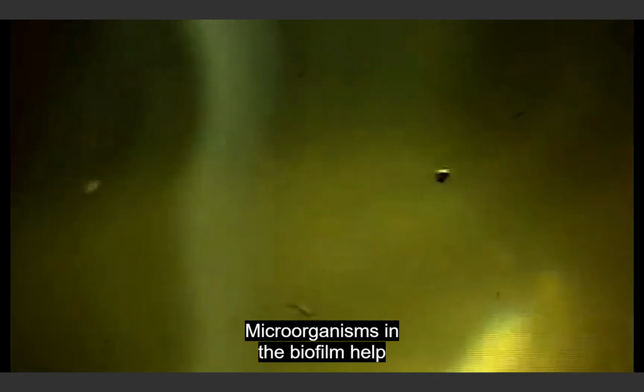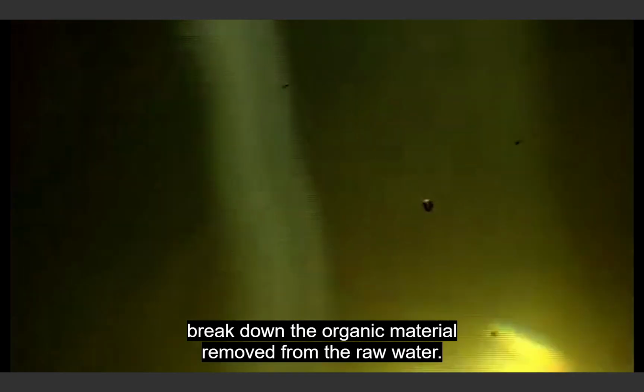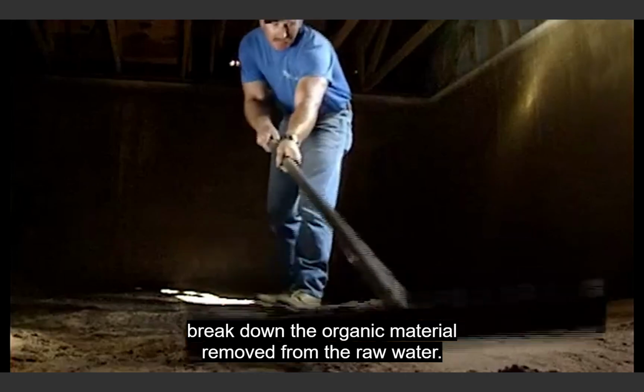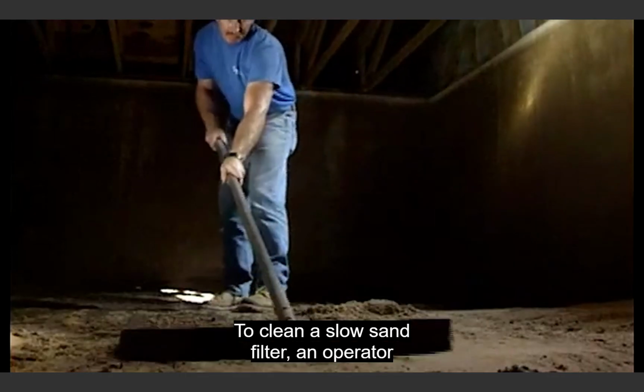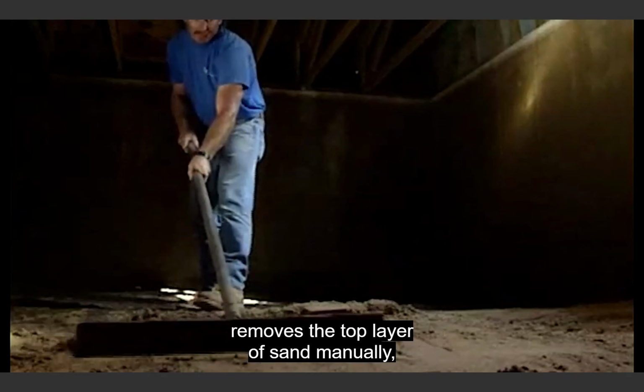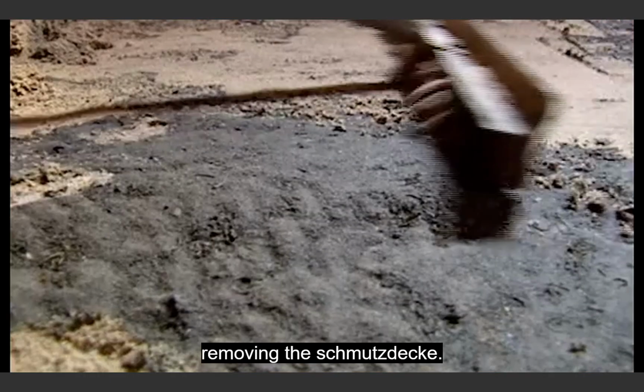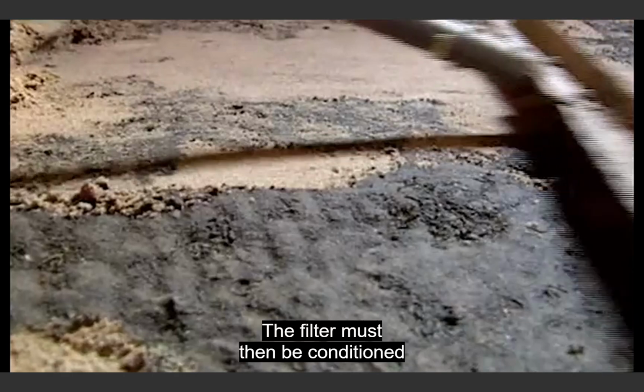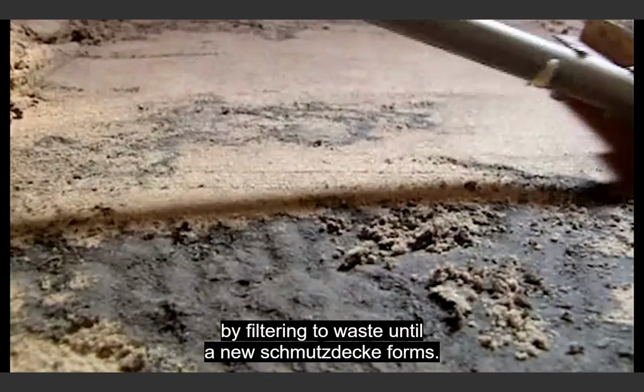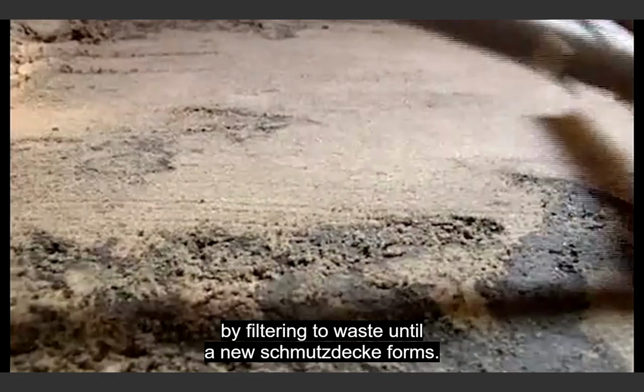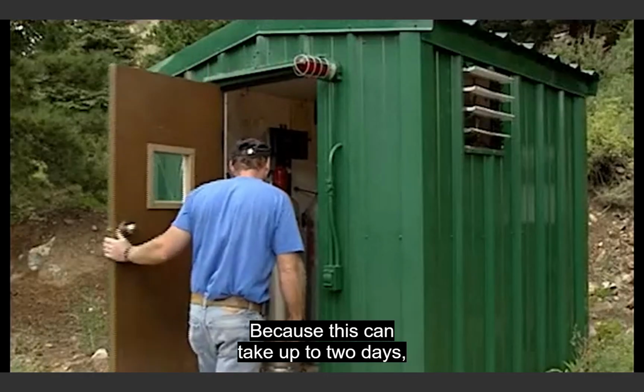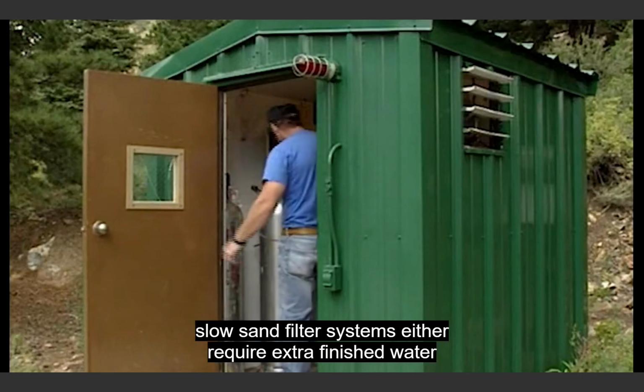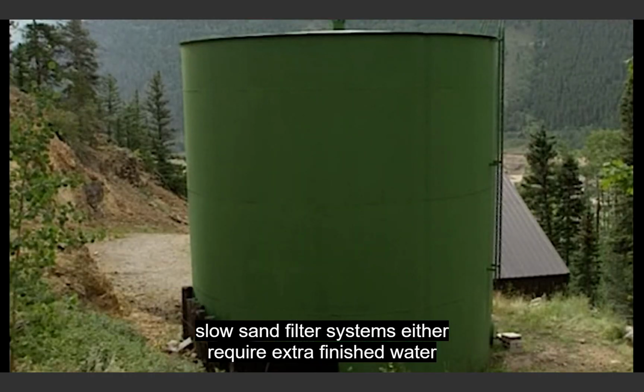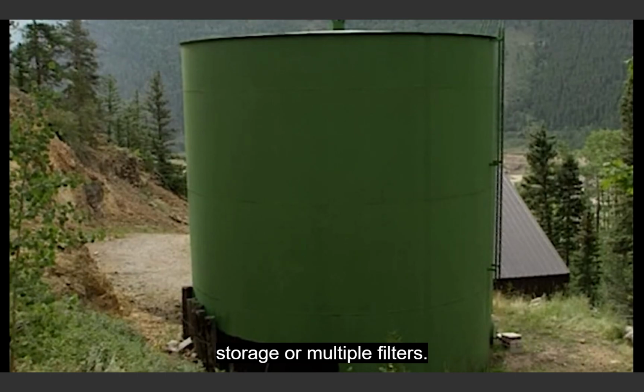Microorganisms in the biofilm help break down the organic material removed from the raw water. To clean a slow sand filter, an operator removes the top layer of sand manually, removing the Schmutzdecke. The filter must then be conditioned by filtering to waste until a new Schmutzdecke forms. Because this can take up to 2 days, slow sand filter systems either require extra finished water storage or multiple filters.